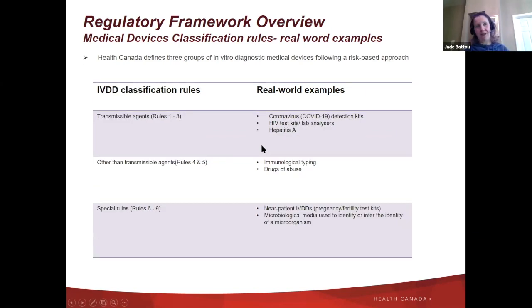For in vitro diagnostic devices that use human samples to diagnose, we have those that fall under rule 1, 2, 3 for transmissible agents, and others for anything other than transmissible agents, under rules 4 and 5. Special rules fall under rules 6 to 9. For example, near patient IVDDs like pregnancy or fertility test kits are class 2 devices, even though they are home use devices. Normally any home use device is class 3, but for pregnancy and fertility tests, they are class 2. These are examples of devices and the classification rules under which they fall.